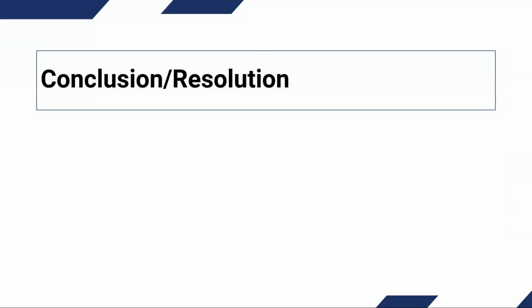On this particular project, our conclusion and resolutions, well, first thing we had to do is repair all the mechanical issues. If we have compressors that are failing on these makeup air units and we can't condition the outside air, that's going to kill us. And in our region, at least, the primary cause of humid buildings is the unconditioned outside air. We've got to bring in a pretty good amount of outside air to meet code to keep buildings positive. And if we're not conditioning that air, it's always going to be a problem for us.